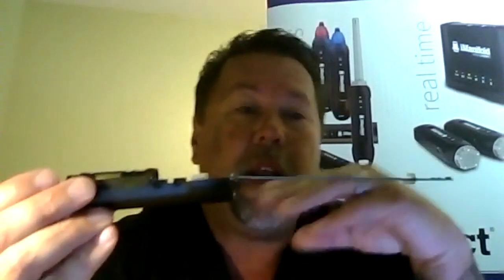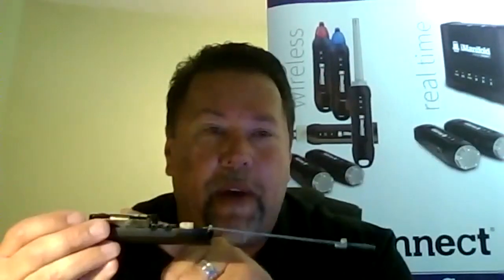Okay, there's your tip in hand. Board is up, and we simply plug it back in. And that's set in there. Now, when you look at it, it's going to look kind of funny because the boards don't match up. That's exactly the way it needs to be. Batteries up, sensor tip up. Okay, just remember that. Then you can put the probe back together. And run this back up. Slide that over. Little dab of silicone on here just to make sure. Take your cover, place it back over the top, and go ahead and reinstall your 4 screws. You'll be ready to go.